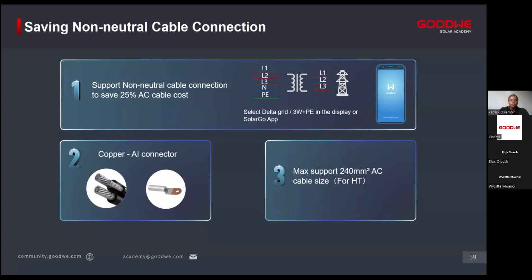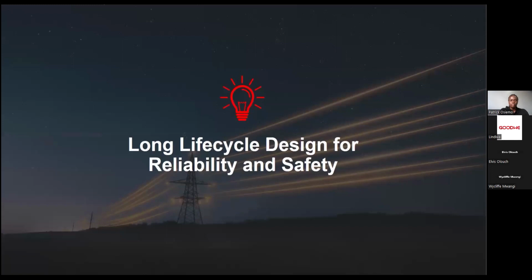Our terminals are big. Take, for example, the HT: each terminal can hold up to 240 square mm AC cables. So yes, aluminum cables do work with our inverters as well. Copper or bimetallic plugs are allowed to be connected to the AC terminals of our inverter.